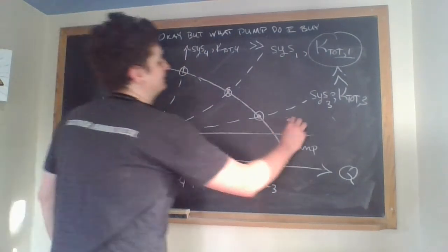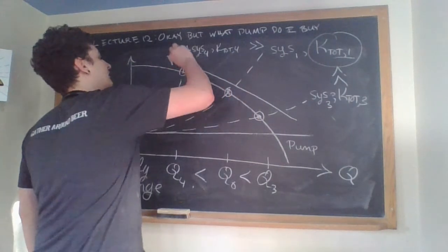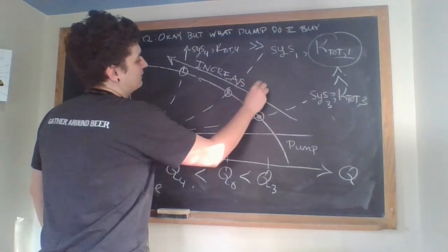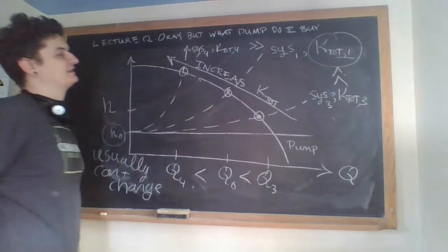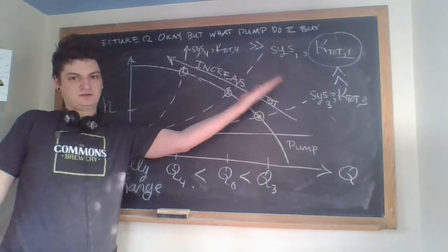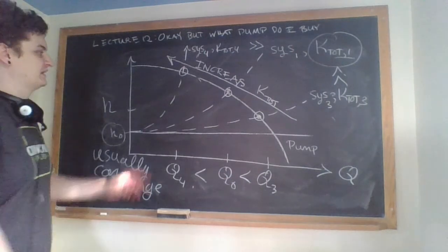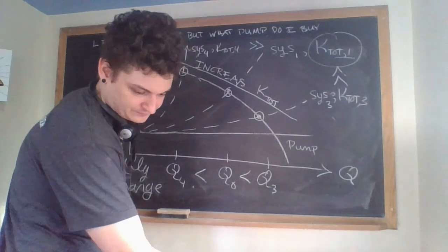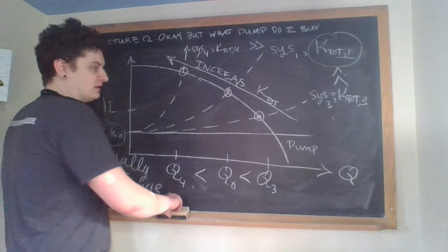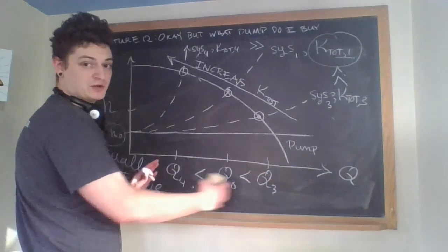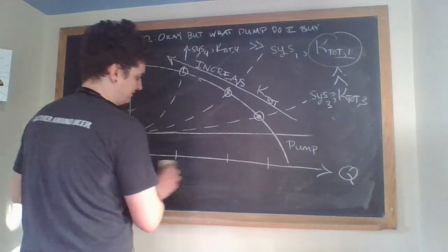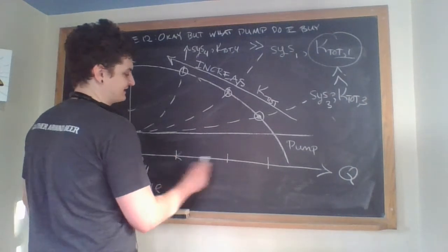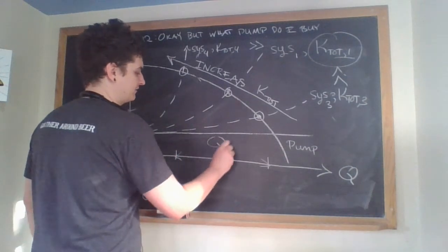Anything else? So in summary, this is increasing the K total of the whole thing. You're just curling that system curve up, because this was a quadratic polynomial in your system design. So you can see with systems that you can move this flow rate around. I gave you 2 ways to actually do that, and there's another design way of multiple pumps. But you get a sense that you can shift this operating point around.